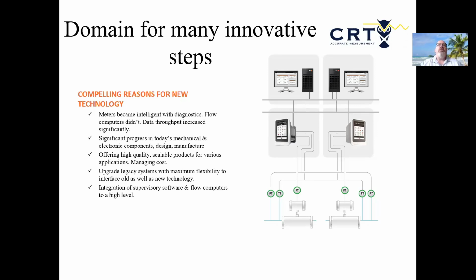When you look at some of the flow computers out there, you have tens of thousands of pieces of information available. Typically off most flow computers, we bring back temperature, pressure, density, flow rate, and some totals. There's a wealth of information that doesn't come back in. We're looking at that more and calling it measurement data, as opposed to your typical SCADA data that brings back normal process information you'd see on a pipeline - flow rate, temperature, and pressure. There's just so much more data we're able to get out of today's systems.